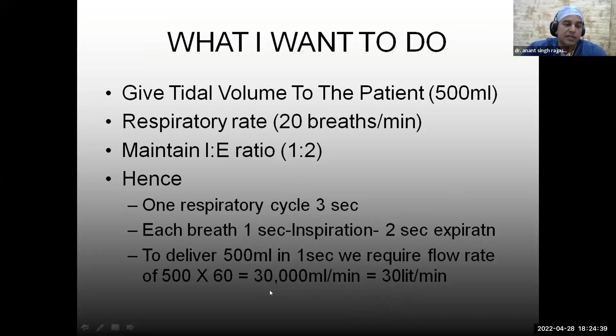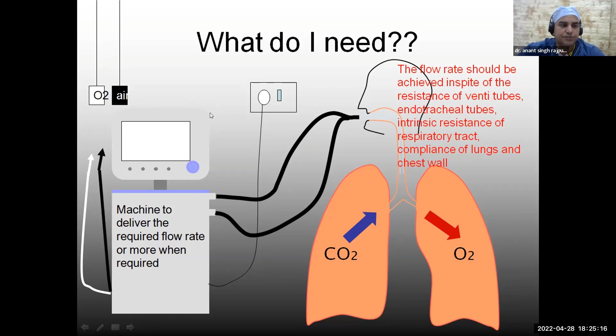If you go on increasing the respiratory rate and changing the I:E ratios, your time for giving the tidal volume will go on reducing, and the flow demand may increase from 30 liters per minute to maybe 60 liters per minute. Right? To meet such a flow demand, you require a machine that works with higher pressure. So we are having this. This is a higher pressure. In anesthesia, what happens? We convert this to intermediate, then to a low pressure system in our circuit. But here in the ventilator, we do not do that. The low pressure system starts after the machine directly towards the patient. So we are supposed to deliver very high flow rates, and that can only be done by using high pressures. We'll be talking about it further in the next few slides.